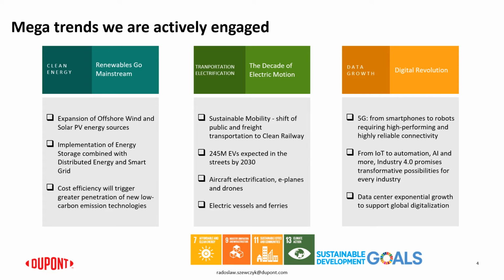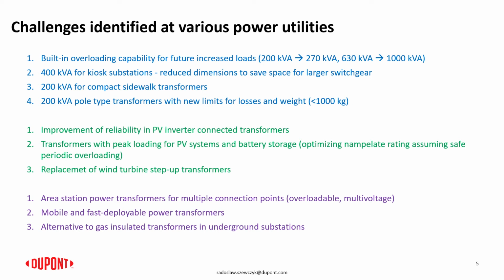If we look at the specific requirements for the transformers, we can see the needs in the increased loading of the transformers. So the transformers that have certain capacity today, they are expected to be loaded more in the future, and that's why current specifications for the transformers require more overloading capability or higher rating within the same physical size of the transformers.